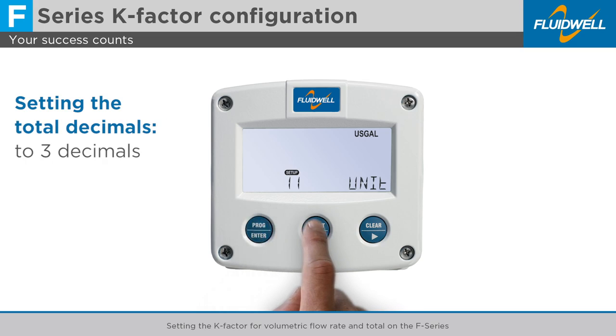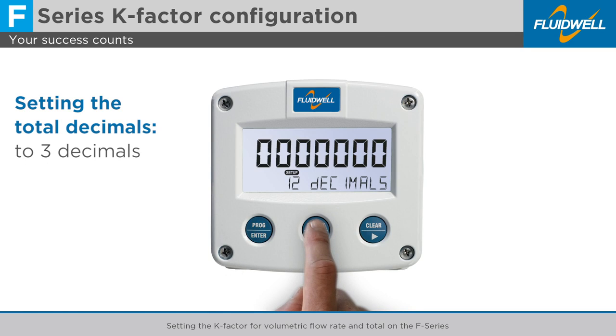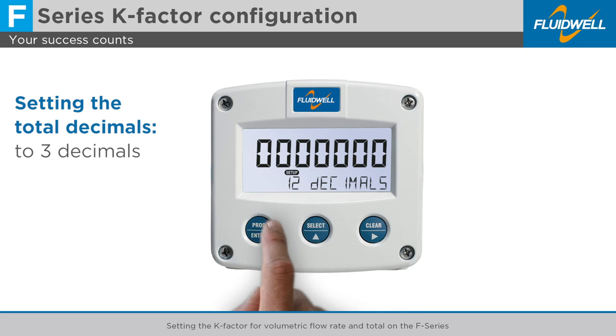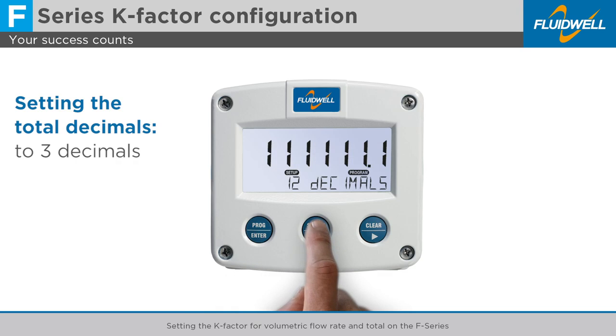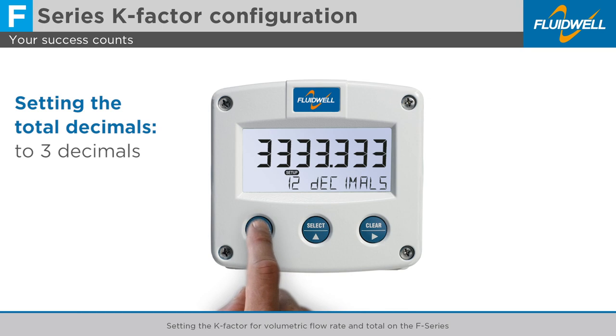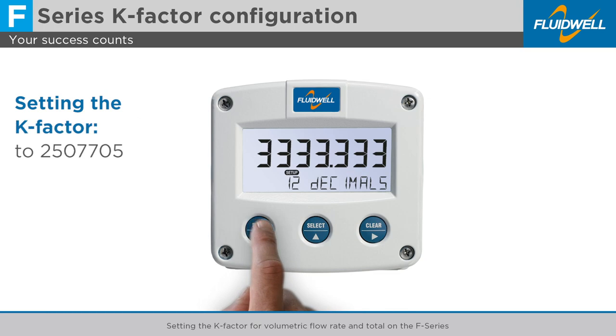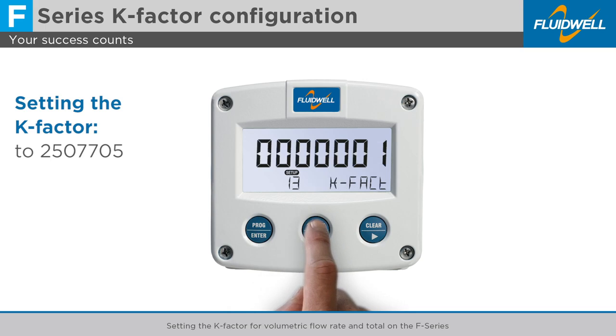Now use Select again to go to Menu 12 Decimals to select the number of displayed decimals for the total. Press Prog to change this setting. Select 3 decimals for an accurate reading in the display. Press Prog to store this setting. Use Select to go to Menu 13 K Factor.